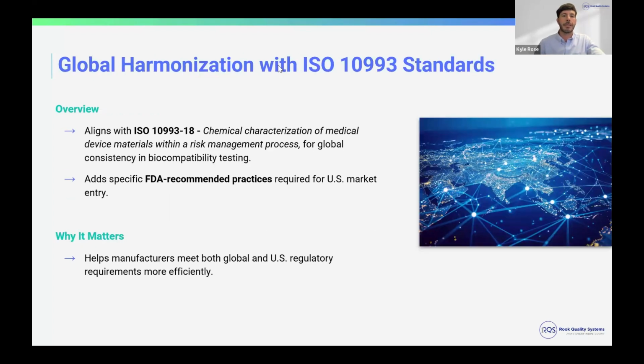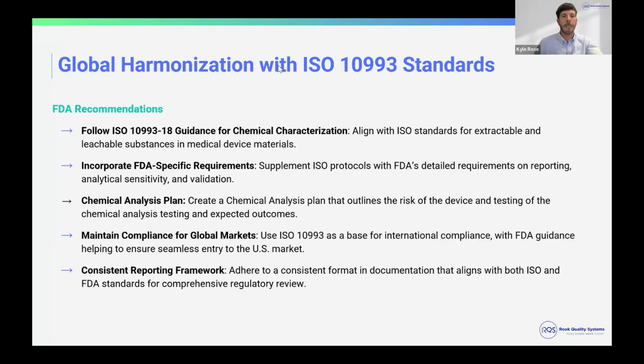This new guidance is also designed to align with ISO 10993-18, which is the chemical characterization of medical device materials within a risk management process. So it is aligned to not only meet the requirements for the FDA, but also meet the requirements for ISO and other international markets as well. So it helps manufacturers meet the requirements for both FDA and ISO 10993-18 with one set of testing.